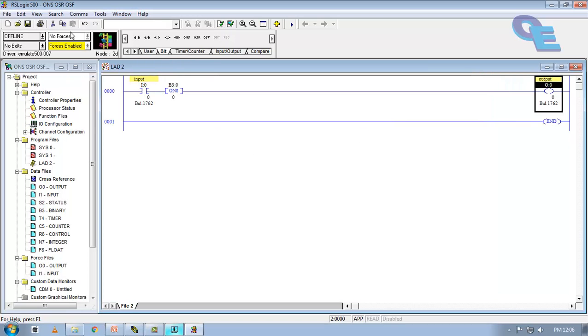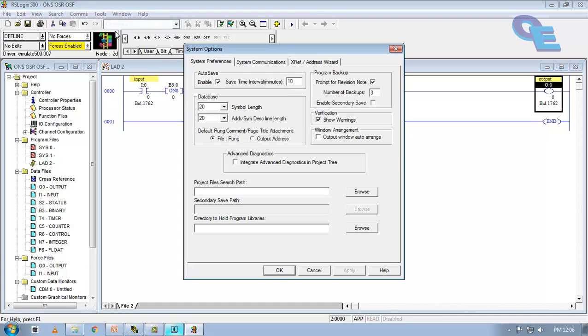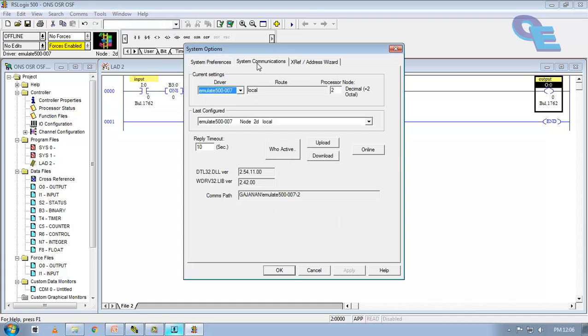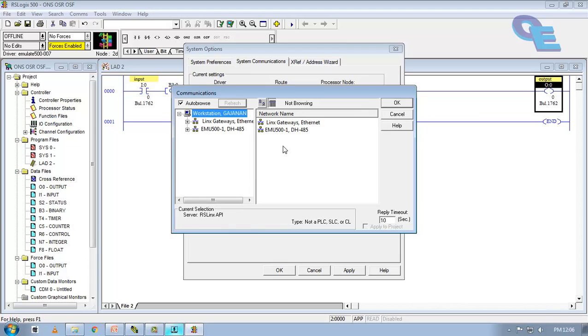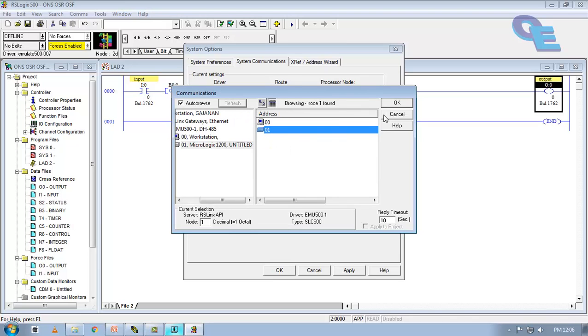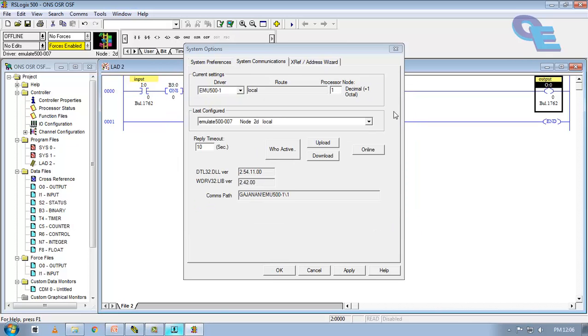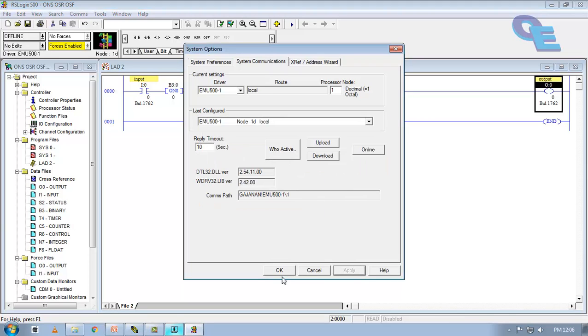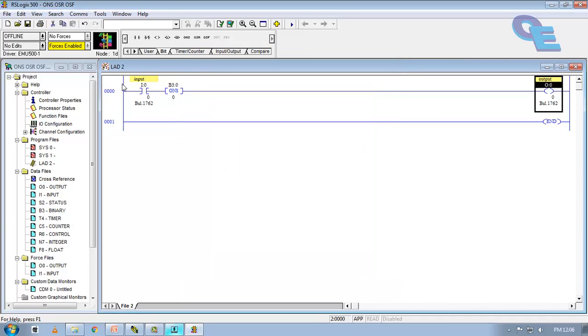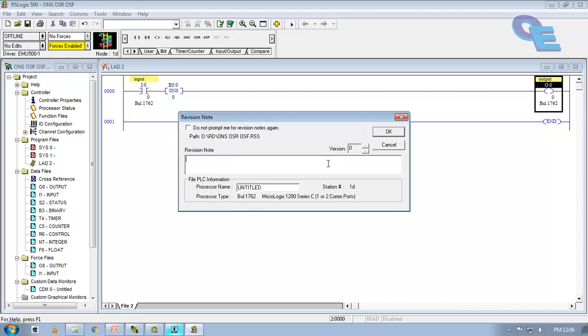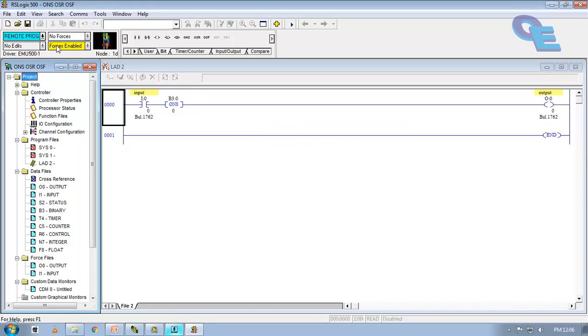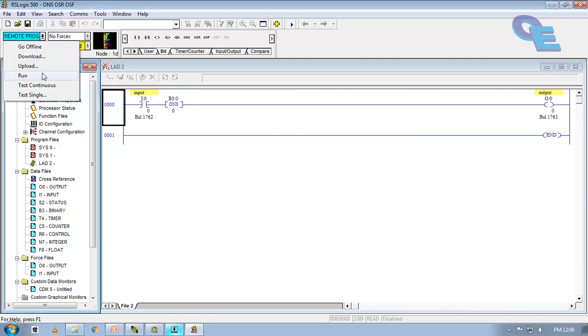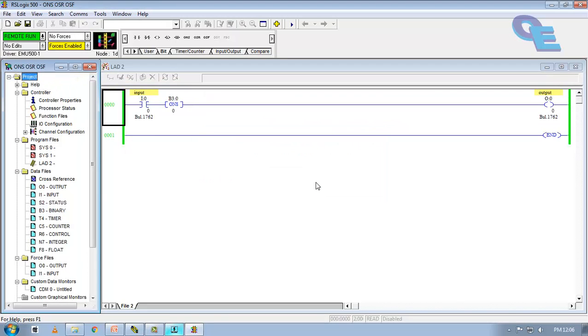Now, go to tools, options, system communication, select the driver type here. EMU500-1 and click on OK. Here you can see the station number that is 01 and click on OK. Apply. Now go to online and save changes. Now click to run.